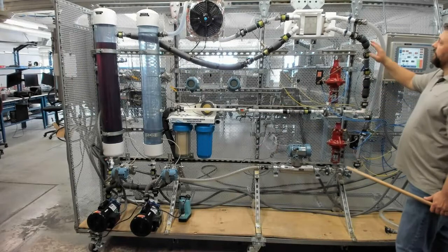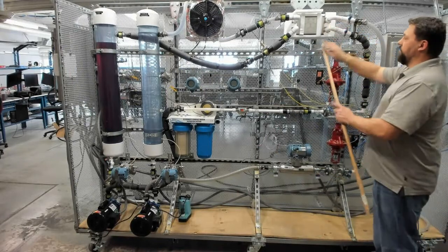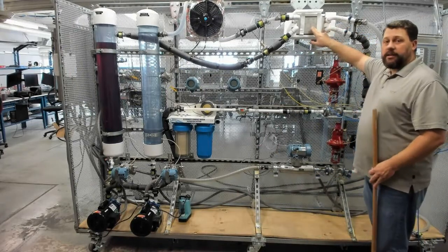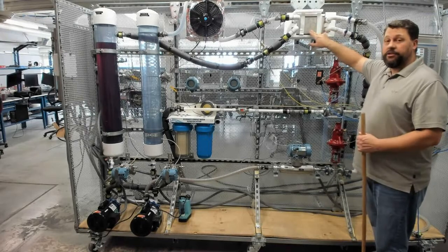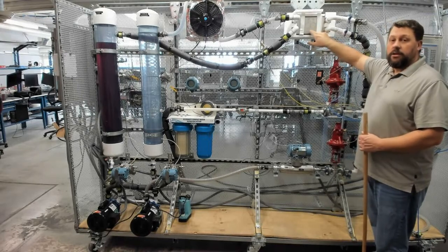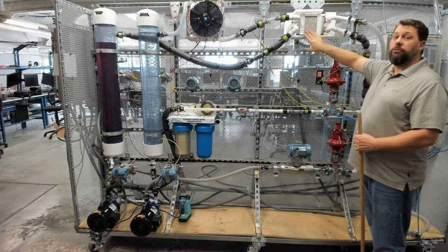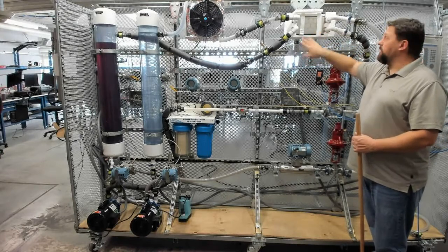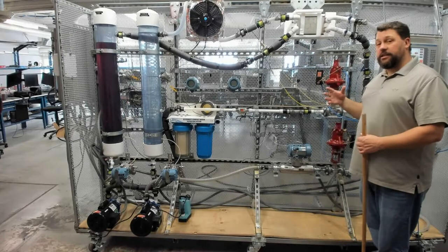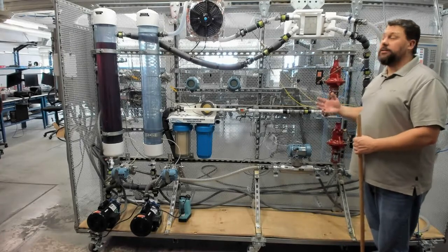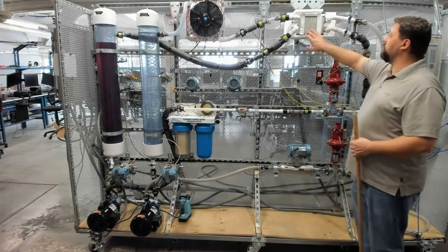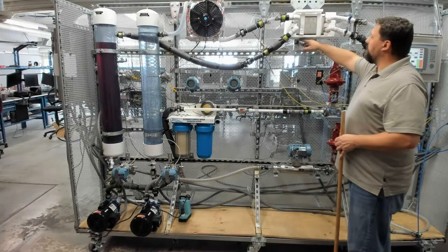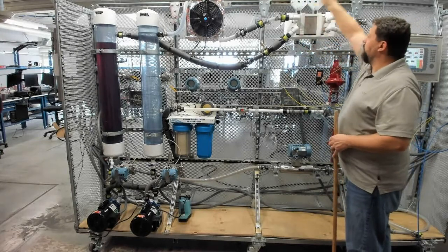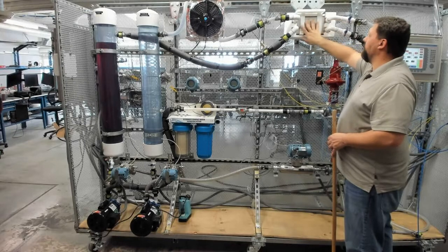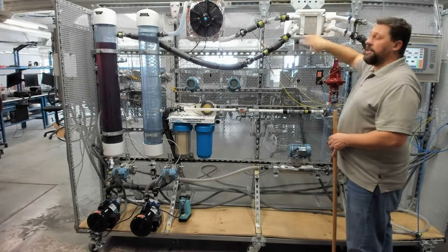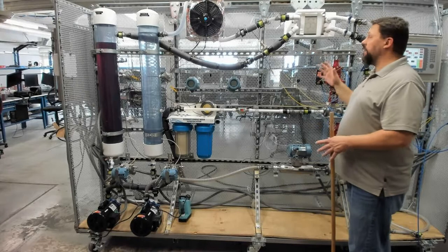We come through here, and we come into the plate heat exchanger. This is an important concept here: plate heat exchangers, all heat exchangers, are passive components. You can't really adjust what the heat exchanger is doing. It's a passive component. What we can adjust is the flow rate through the heat exchanger. We have styrofoam insulation. We have one piece off so you can kind of see in there. We have styrofoam insulation, so the heat exchanger is not affected by the ambient air temperature.